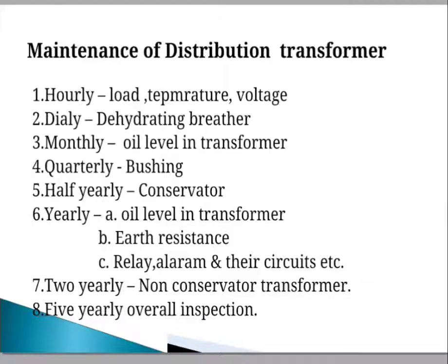Then the next one is the five yearly basis. We have to carry out an overall inspection of the transformer, and lift the core and coils. Then wash with dry oil or wash properly according to the requirement, or dehydrate the moisture content from the transformer.